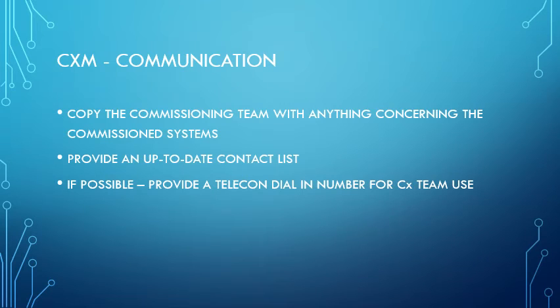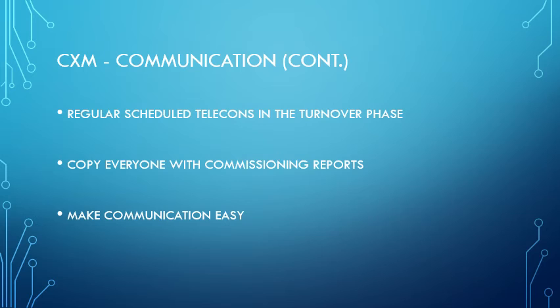For commissioning communication, copy the commissioning team on anything concerning the commissioning system, and provide an up-to-date contact list. For example, for the chiller, who is the supplier, who is the maintenance team for the supplier, who can we contact, and likewise for electrical and plumbing. Everything in the contact list must be up to date. If possible, provide a telephone dial-in number for commissioning team use. We must also regularly update the telephone numbers in the turnover phase, for example if the maintenance team changes. Copy everyone on the commissioning report and make communication easy.